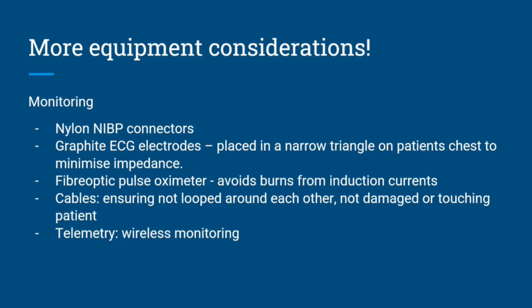Other equipment, as Kath mentioned about monitoring: everything is generally telemetric, so it's wireless. You need different NIBP connectors. Electrodes are generally placed in the middle of the patient's chest, where you would do CPR, I think, and they're different electrodes, as well as a different type of fibre optic pulse oximeter. If there are any cables, we need to ensure that they run down the middle of the patient and are not looped or thrown around each other, because they can generate currents within the MRI scanner. They should not directly touch the patient, and the cables should not be damaged.